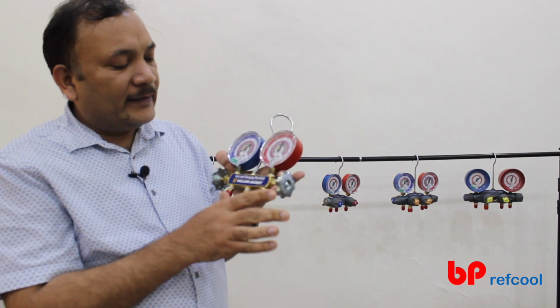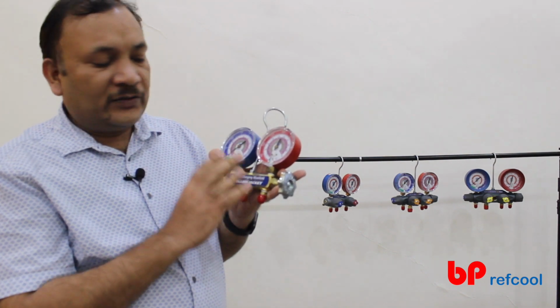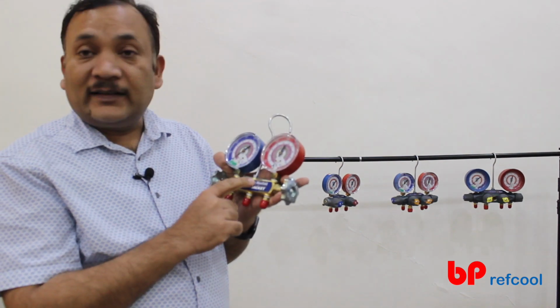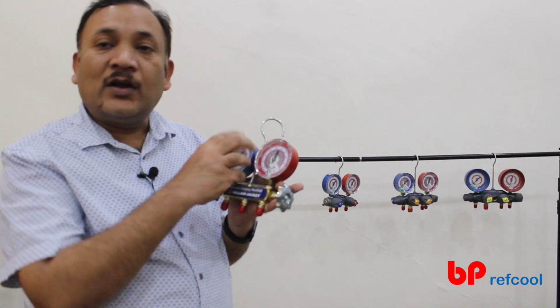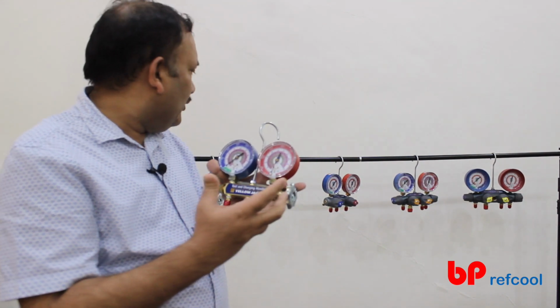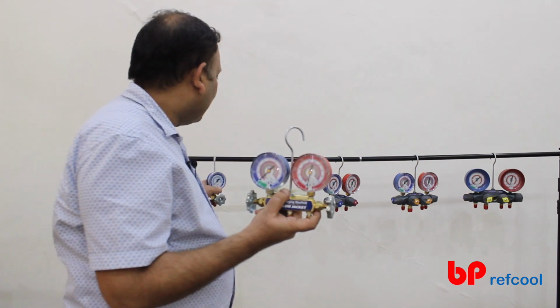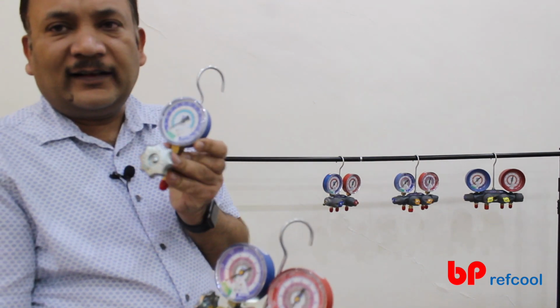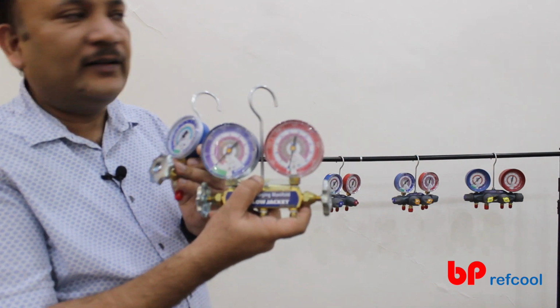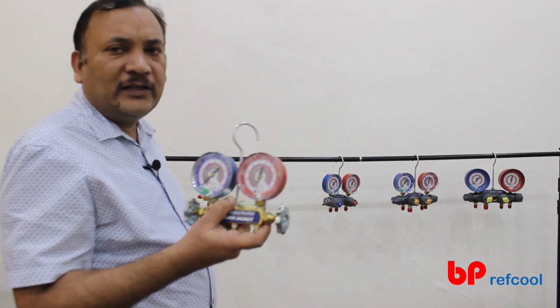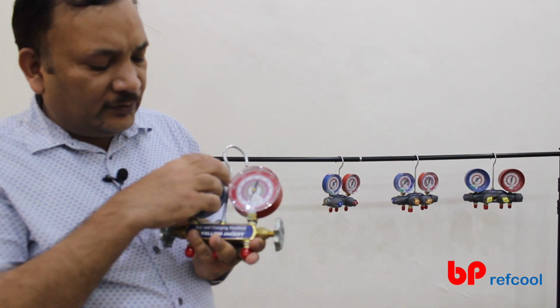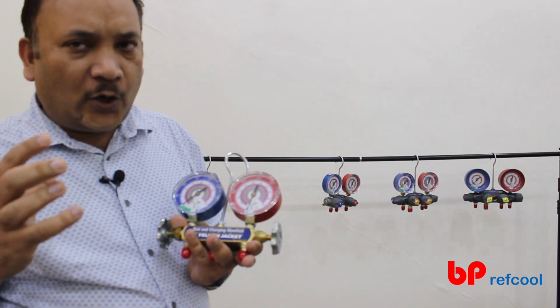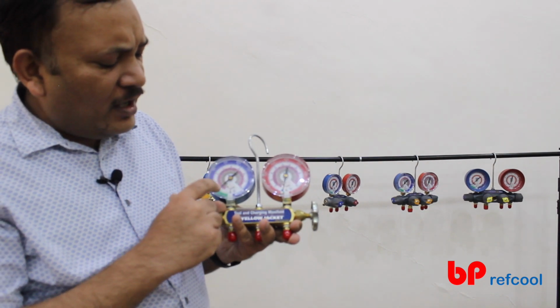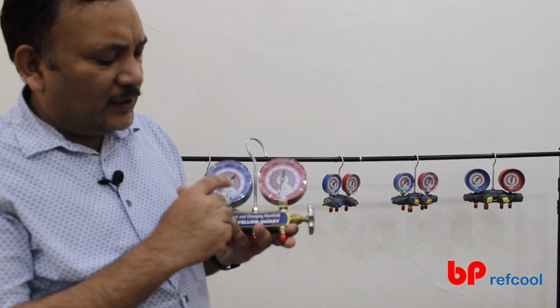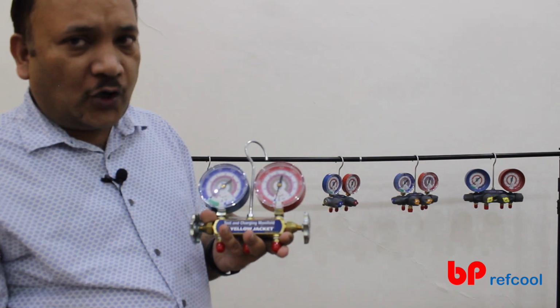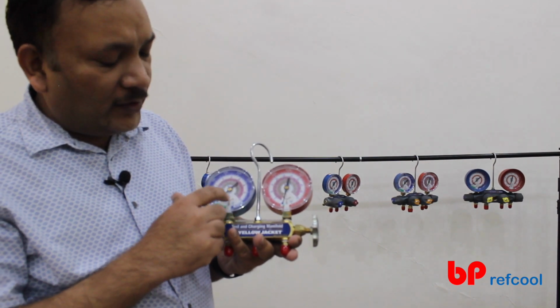The other important part is the material of construction, whether it is brass or aluminum, whether there is a sight glass or not, what type of gauges are used, and what size of gauges are used. Normally you will see a small gauge, which can be a 2-inch gauge like this one, versus this 80 mm gauge. An 80 mm gauge is slightly bigger and easier to read. Then, within the gauge, what units are available: degree centigrade, PSI, which is most commonly used here in India, and then the different refrigerants.